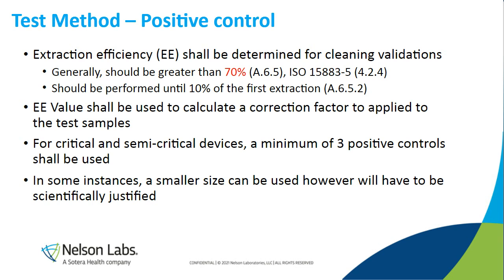Another thing for the positive control is the reusable industry has always been okay with doing just one positive control with the test sample. It is required that you need a minimum of 3 positive controls now. And like I say, the language says "shall be used," so that means you will have to use at least 3 positive controls.